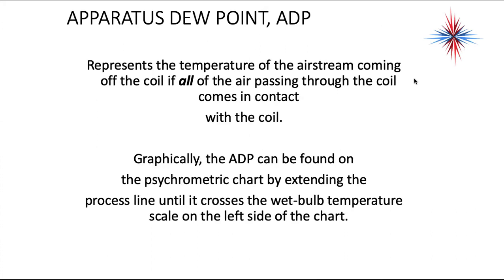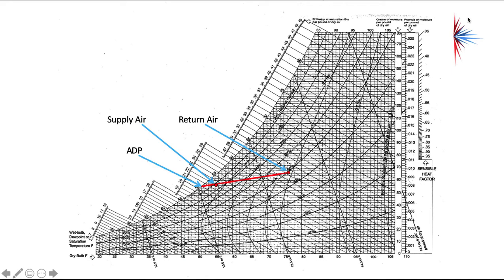The apparatus dew point, or ADP, represents the temperature of the airstream coming off the coil if all of the air passing through the coil comes in contact with the coil. Now, this actually rarely happens that all of the air passing through comes in contact. Graphically, the ADP can be found on the psychrometric chart by extending the process line until it crosses the wet bulb temperature scale on the left of the chart.